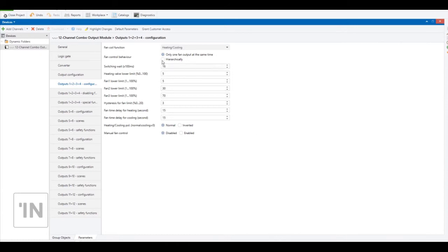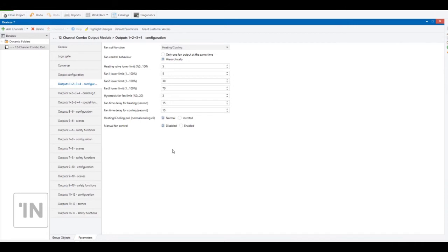When you choose 'hierarchically,' it works on a different principle. For fan level one, it opens only channel one. For fan level two, it opens channel two but does not close channel one — so fan level two uses channel one and channel two. For fan level three, it uses channel one, channel two, and channel three together.